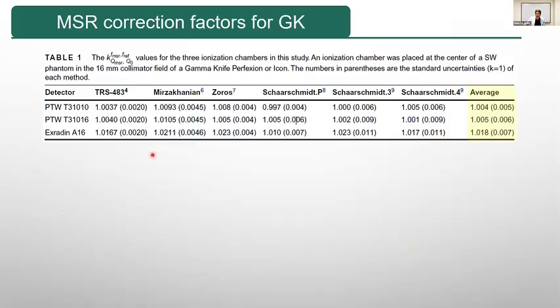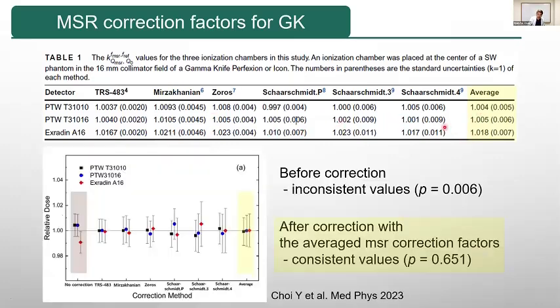The important thing is the correction factor values. So I checked the dose rate of these 3 ion chambers before and after correction. For correction, I used the TRS-483 recommended values, other studies, and averaged values. This graph shows the relative dose rate of these 3 chambers before correction. They are not constant at all, but when we apply the average correction factors, these 3 chambers produce constant values, at least statistically constant values with a p-value of 0.65. And even though the TRS-483 was a little bit worse than the average value, it also produced very good results.